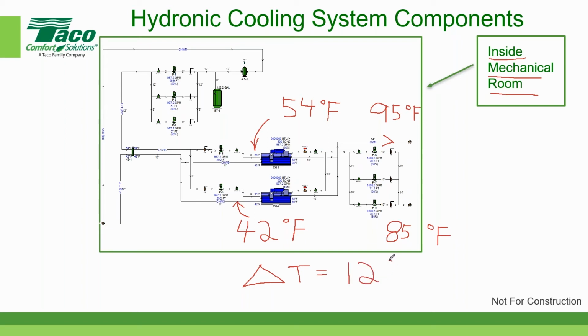Whenever you have a system where your chilled water delta T is 12 degrees Fahrenheit, it translates into, you ready for this, Brett? 2 gallons per minute, 2 GPM per, drum roll, please, per ton. There you go. 2 GPM per ton. So in a 1,000-ton system, we should be pumping approximately 2,000 GPM. If you look over here, I know you can't see the numbers because they're tiny, but it says 997.2. That's because the software calculates it based on the mass rate of flow and then converts it into gallons per minute based on the temperature. So 1,000 there and 1,000 here approximately, that's 2,000 gallons per minute.